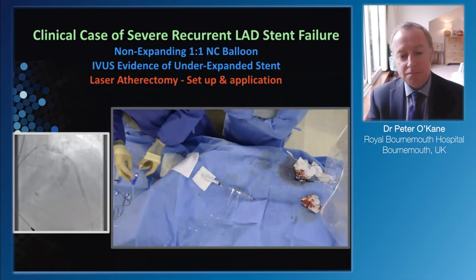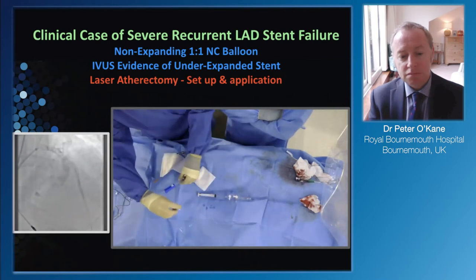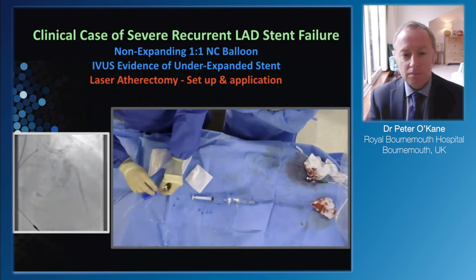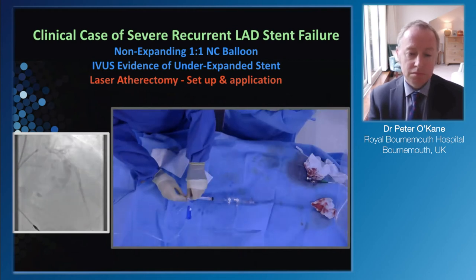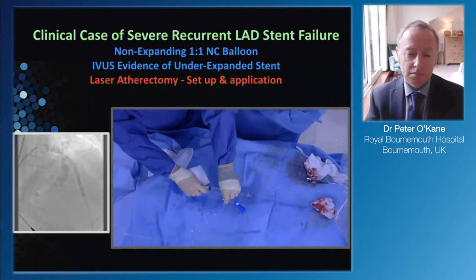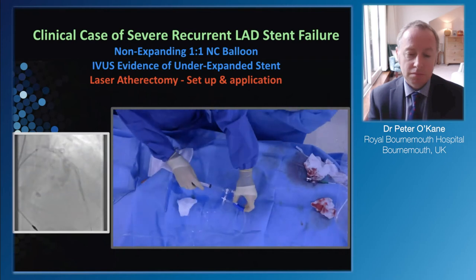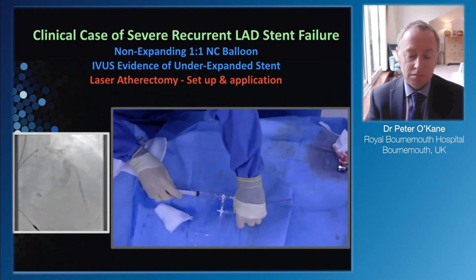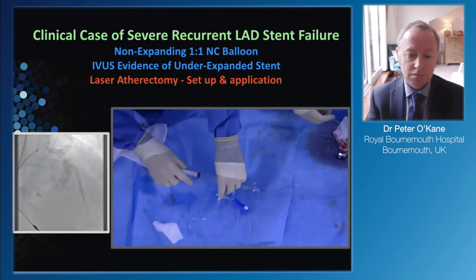Back to the case - how we do it in this lab. We set up with a three-way tap: saline on the side of the tap, then disconnect the contrast and put it on top of the three-way tap, then reconnect the contrast line back to the manifold. This gives us full control of saline and contrast. Contrast goes straight, saline comes out the side. The saline's now turned on - it doesn't need to be under pressure, unlike a rota system, because we're only using it by pulling back on the syringe.